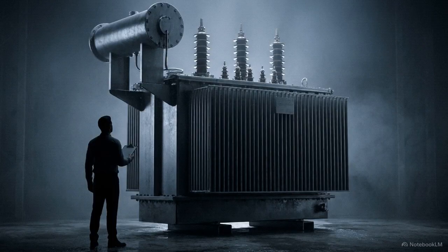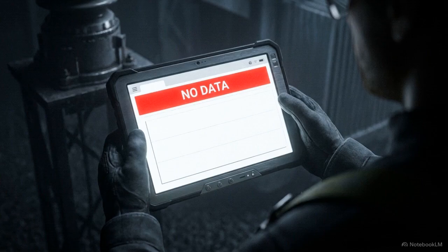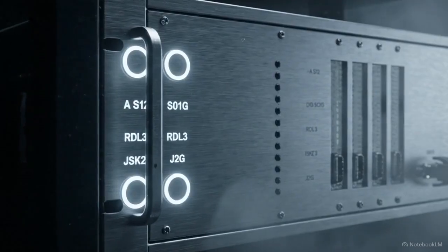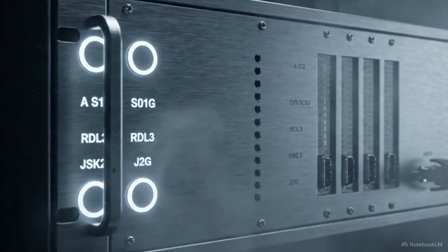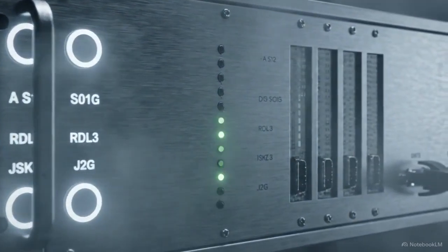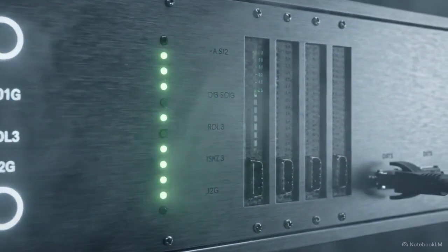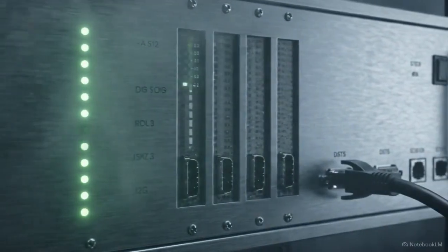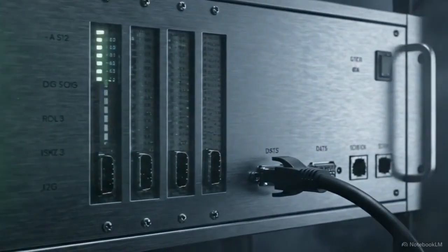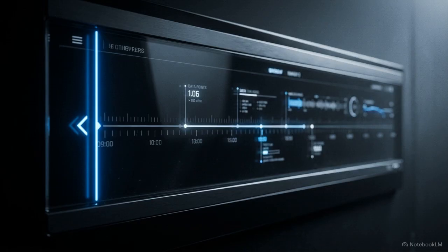This presents an engineering dilemma. How can grid operators avoid a magnetic hazard they cannot physically see or measure once the power is off? The solution is the point-on-wave, or POW, controller, a diagnostic computer that monitors and logs the transformer's magnetic state during every switching operation. To figure out what's trapped inside the core, the controller has to step back in time.